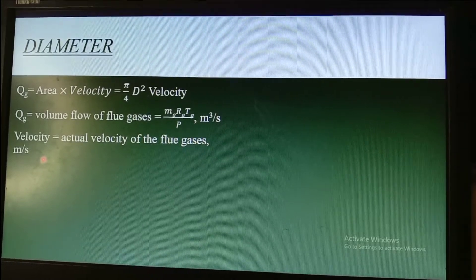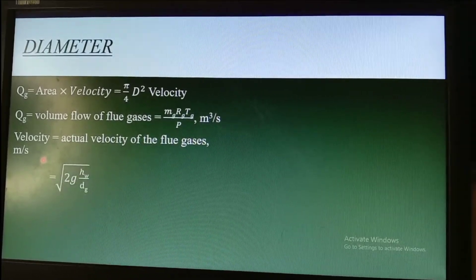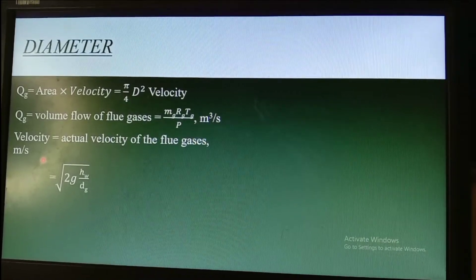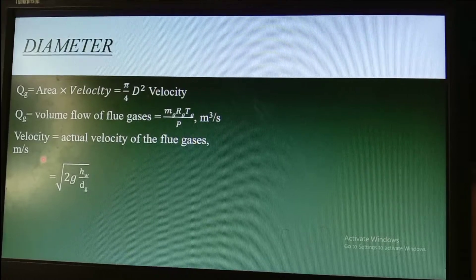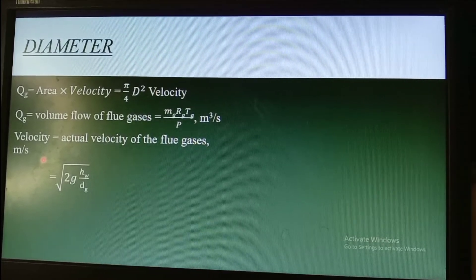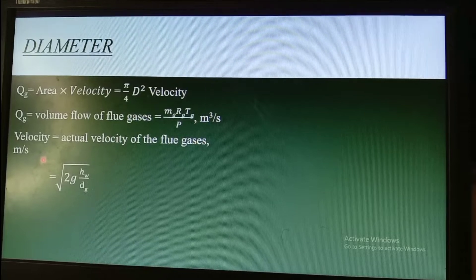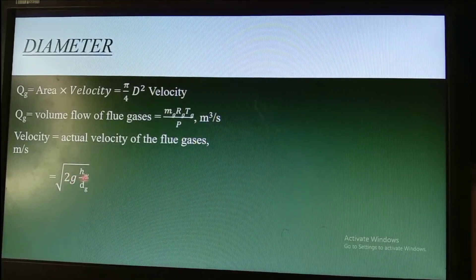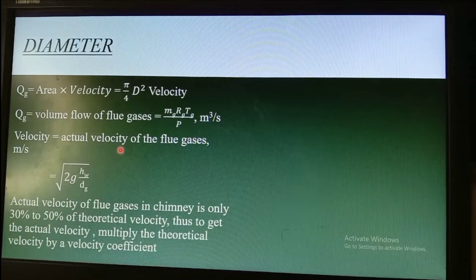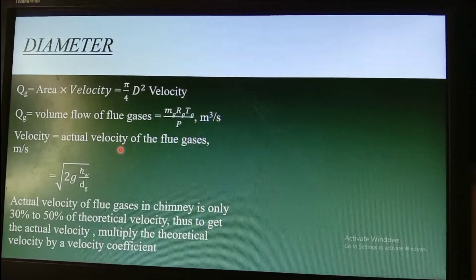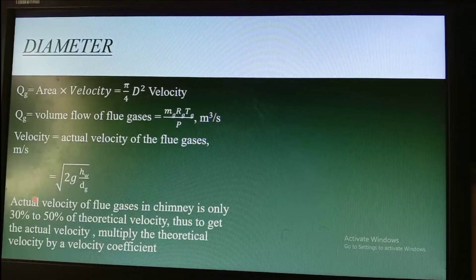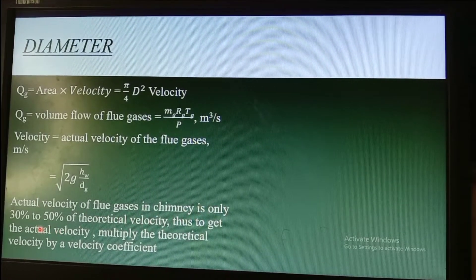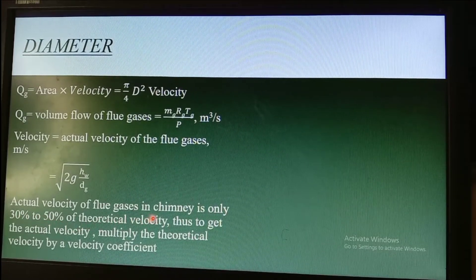The theoretical velocity is equal to the square root of 2g times the pressure drop divided by the density of the flue gas. The actual velocity of flue gases in the chimney is only around 30 to 50 percent of the theoretical velocity.